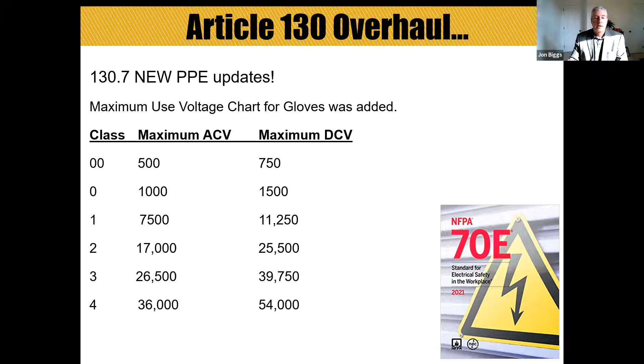Next, a final thing about PPE updates is the glove chart. They've now included a new maximum use voltage chart for gloves in 130.7. You can see the different classes from double-aught all the way to 4, along with the maximum AC voltage, maximum DC voltage, and those ratings for reference.